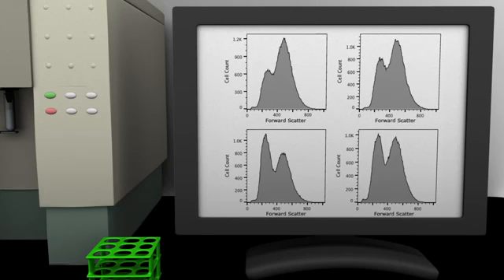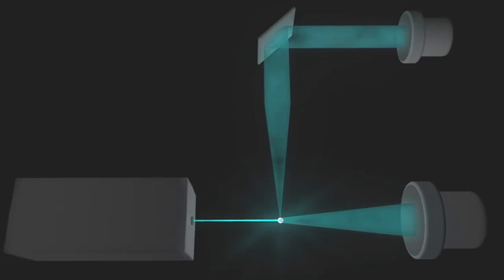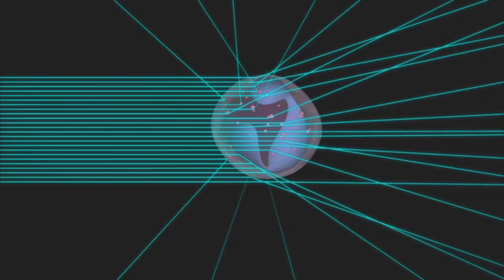The amount of side scattered light is detected by a detector located perpendicular to the path of the laser beam. Side scatter is proportional to the shape and internal complexity of a cell.